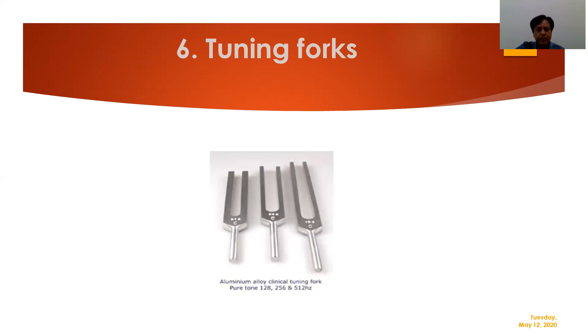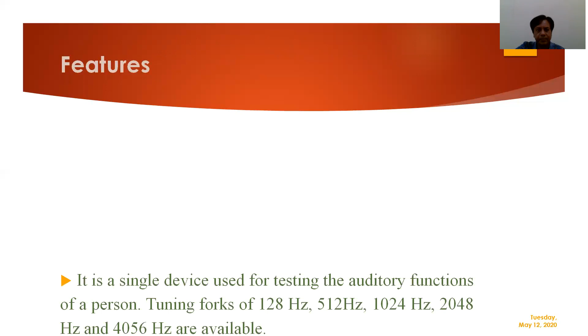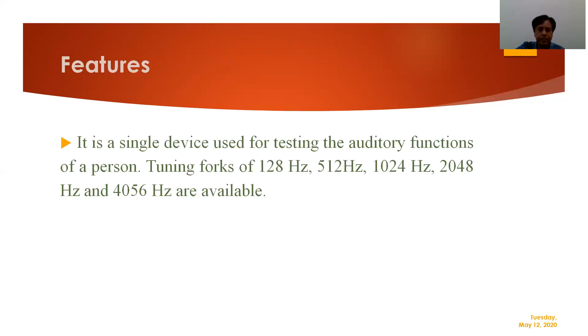Then tuning forks. These are tuning forks. Its features are: it is a single device used for testing the auditory functions of a person. Tuning forks of 128 Hz, 256 Hz, 512 Hz, 1024 Hz, 2048 Hz, and 4096 Hz are available. Tuning fork having frequency of 512 Hz is the ideal instrument for these functions, as its frequency is same as that of the speech, and duration for which the sound is produced by a single strike is long enough to complete all the tests easily. Forks of lower frequencies cause overtones, and those of higher frequency have shorter decay time. Therefore, tuning fork having frequency of 512 Hz is ideal for the test.